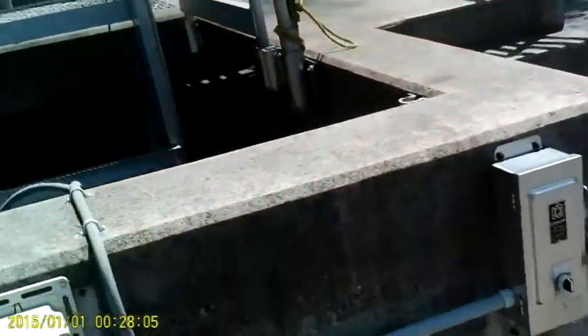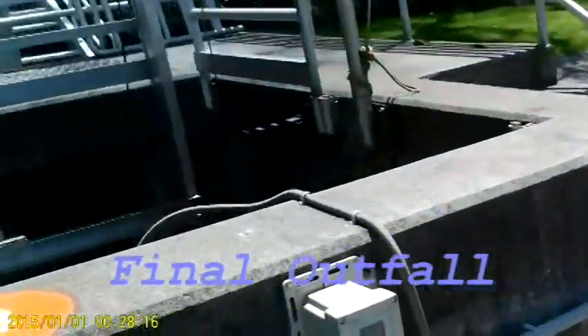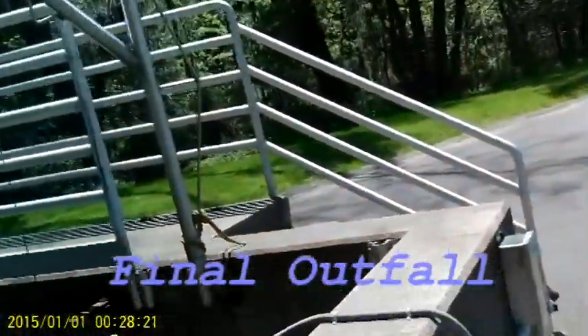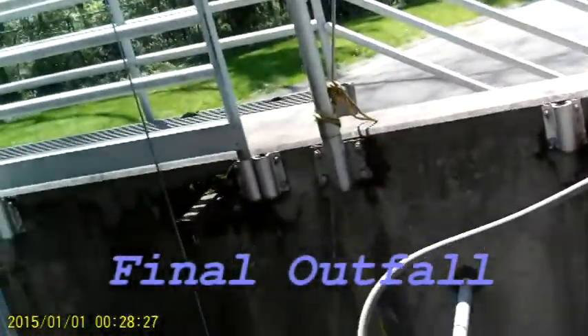We'll go to the controller here, the output, and it's flowing 2.8 million gallons per day. As you can see, the influent was around 4 something million gallons per day, and we're around 3 million gallons per day. So what we're doing is removing about 1 million gallons of water per day on average, which is the fluid containing all the grease, scum, sludge, activated sludge, and then we thicken it and dewater it.